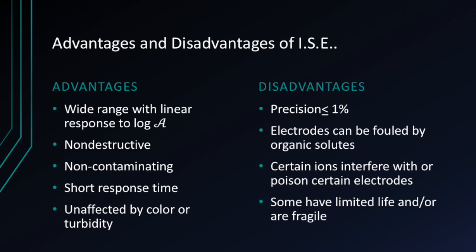Advantages of using an ion-selective electrode include a wide range with linear response, being non-destructive and non-contaminating, short response time, and being unaffected by color or turbidity. Disadvantages include precision of 1% or less most of the time, electrodes can be fouled by organic solutes, certain ions interfere with or poison certain electrodes, and many electrodes have limited life or are fragile.